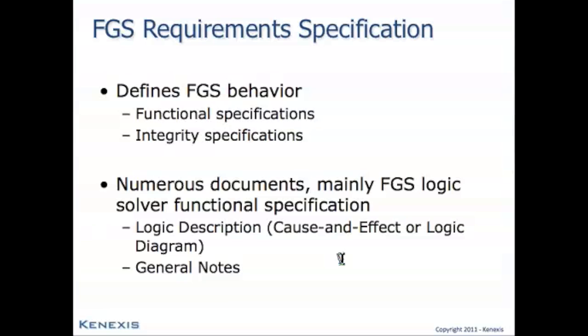Okay, so two of the main documents that will comprise an FGS requirement specification, which typically is going to fall into the logic solver functional specification, would be, number one, the logic description. And far and away the most common method for documenting logic in a fire and gas detection and suppression system is a cause and effect diagram. But in some cases, binary logic diagrams are used, or even other methods such as narratives or simple text.